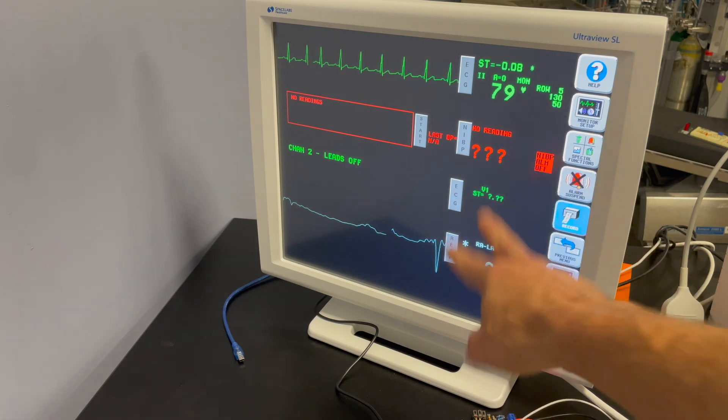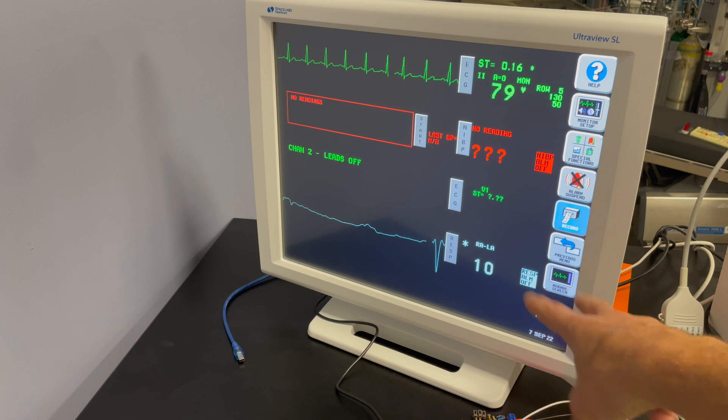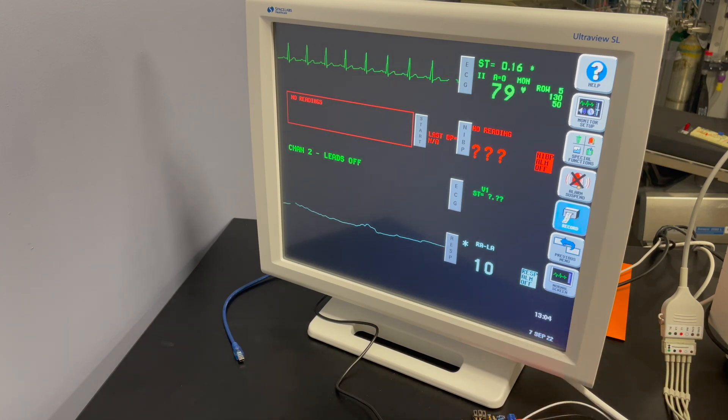Now the respiratory rate down here is just reading some noise right now because I was moving around the cables. But if you want to measure the respiratory rate, you're going to have to make sure you select the correct leads.